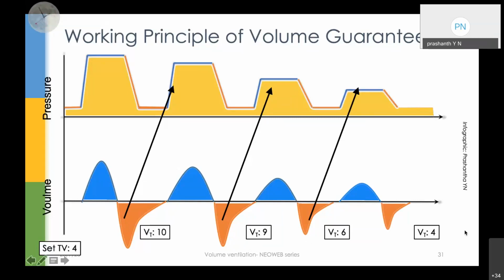So probably to deliver a tidal volume of 4, I should have set a pressure of about here, but I don't know what the pressure requirement was. But the ventilator has come to this point of setting an appropriate pressure so that the set tidal volume is going into the baby's lung. For a Drager ventilator, that is your Babylog 8000, it doesn't do it very drastically. This is just an example from that. It takes each breath and decreases it in a smart way, rather than decreasing it all at once. It takes 6 breaths to normalize the pressure from the initial pressure to here. So it is more gradual. It doesn't make too hurried changes to come to this tidal volume.